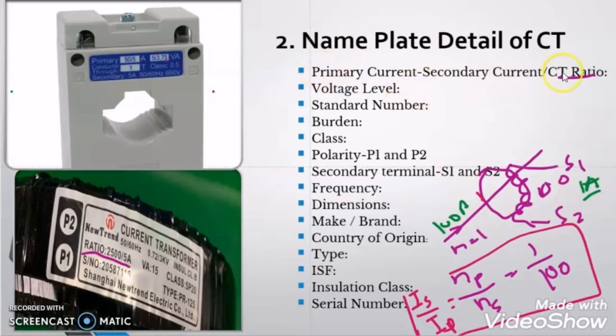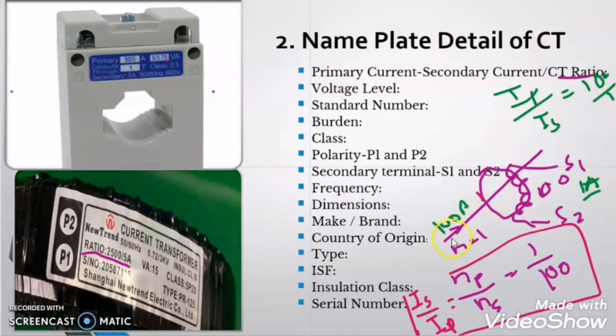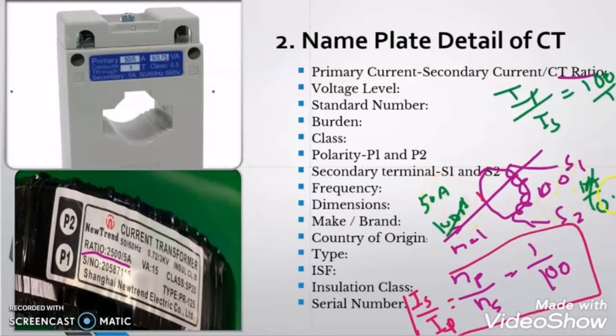So what is CT ratio? CT ratio is the ratio of primary current divided by secondary current. So here we can say that this CT has a ratio of 100 by 1. Because whenever there is 100 Ampere of current flowing through the primary winding — which is the conductor whose current needs to be measured — then there is 1 Ampere of current flowing through the secondary winding. But suppose now only 50 Ampere current is flowing through the primary winding, then there will be only 0.5 Ampere of current flowing through the secondary winding.